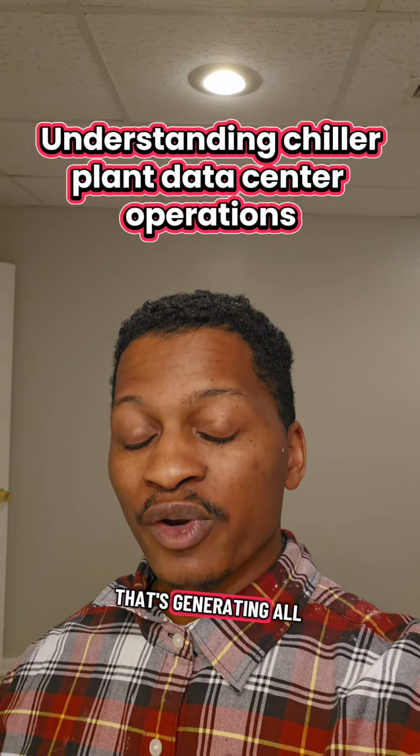With these things in hand, let's say the equipment in the data hall is starting to ramp up, it's starting to do something crazy, and it's causing the heat in the overall space to rise. Your CRAH units are responsible for supplying cold air back into the space. It takes hot air coming in from all the server equipment, and it has chilled water running through its evaporator coils, and it's going to maintain a set point. It is required to blow a certain temperature of cold air back into the space. So as hot air comes back in, if it cannot meet that set point, it's going to open its chilled water valve, allowing more chilled water to come in so it can remove that heat more efficiently and maintain the supply set point.